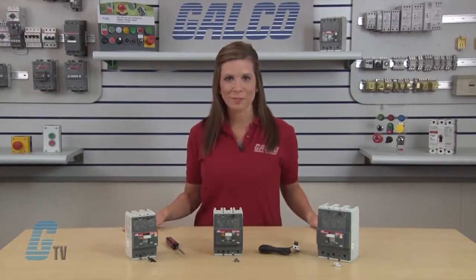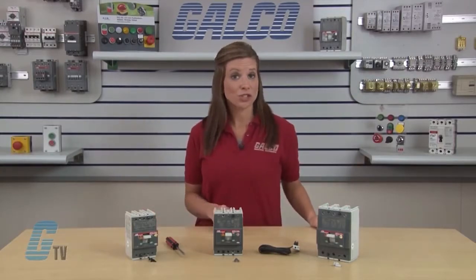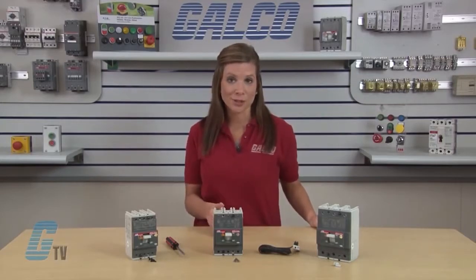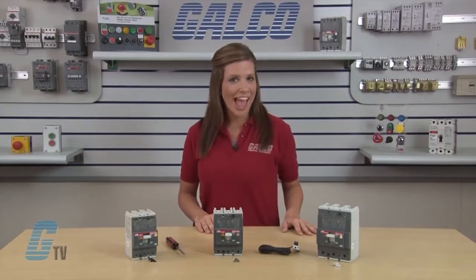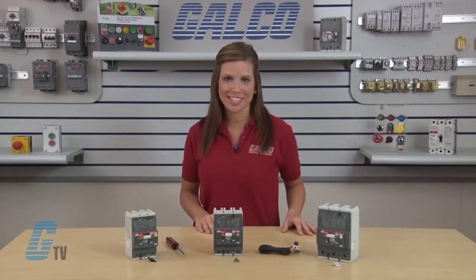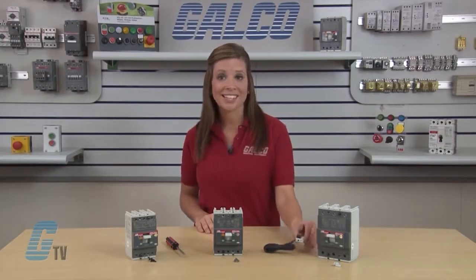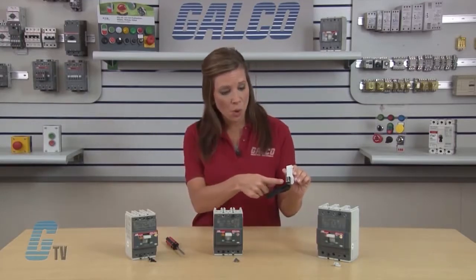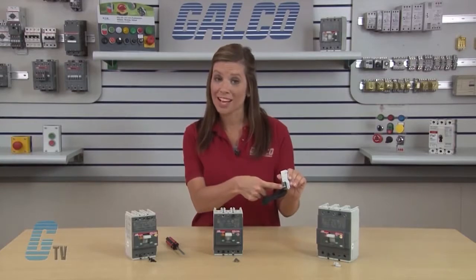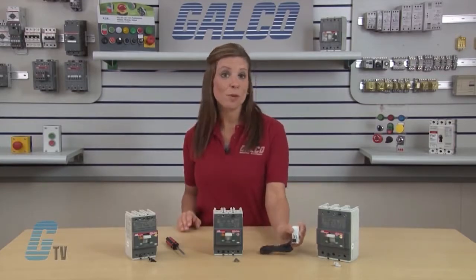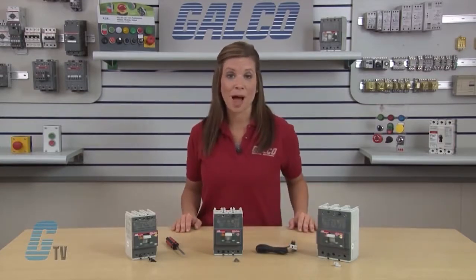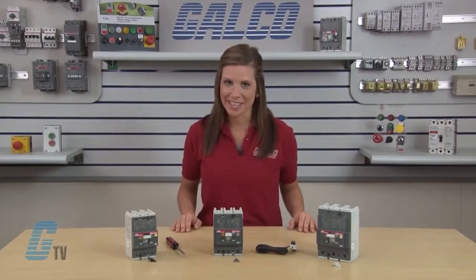These circuit breaker accessories should only be installed with the breaker out of circuit or when all power has been removed from the device, control panel, and anything nearby that may be a hazard to the qualified electrician doing the installation. The auxiliary contact kits come with either 2 or 4 single-pole double-throw contacts, mounting adapters for the T1, T2, and T3 model circuit breakers, and device labels.